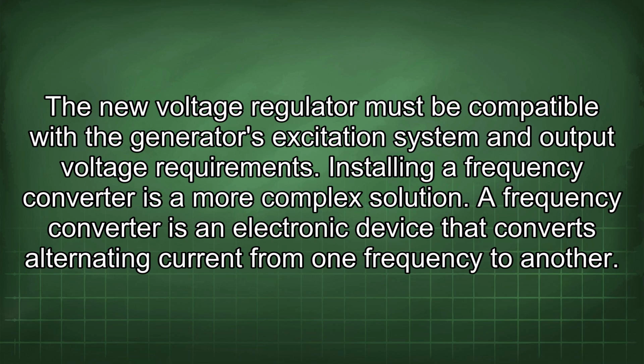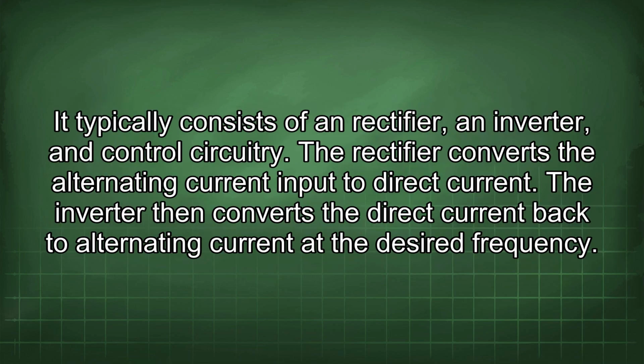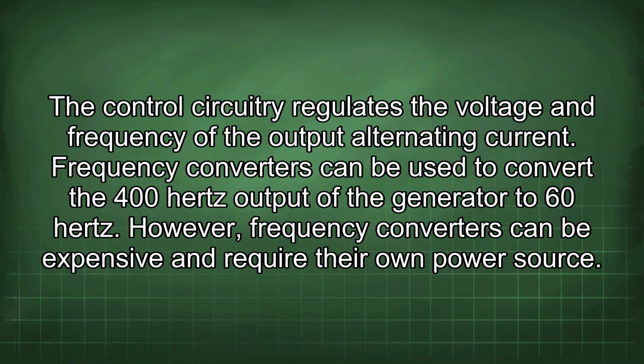Installing a frequency converter is a more complex solution. A frequency converter is an electronic device that converts alternating current from one frequency to another. It typically consists of a rectifier, an inverter, and control circuitry. The rectifier converts the alternating current input to direct current. The inverter then converts the direct current back to alternating current at the desired frequency. The control circuitry regulates the voltage and frequency of the output alternating current. Frequency converters can be used to convert the 400 Hz output of the generator to 60 Hz.